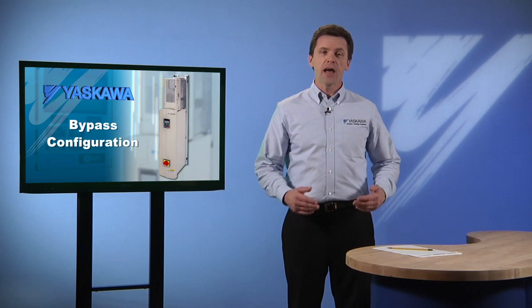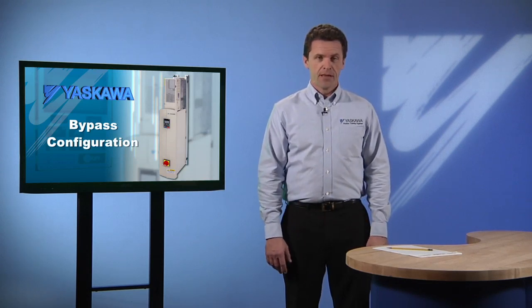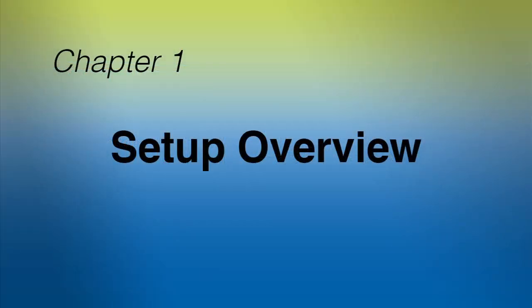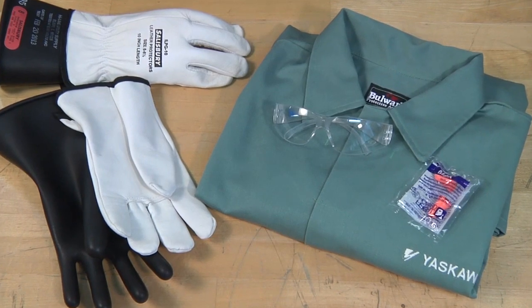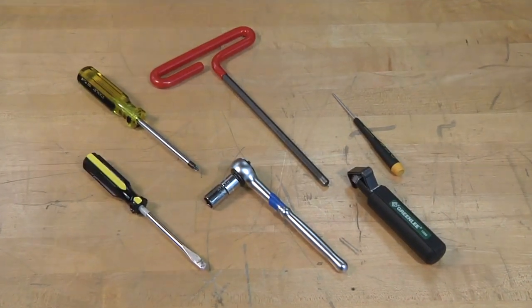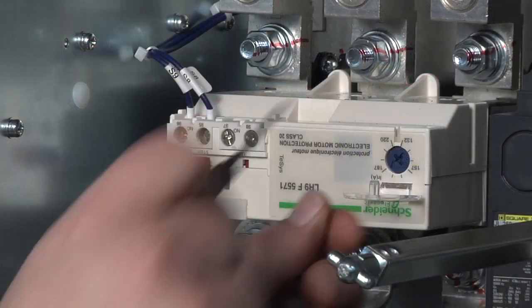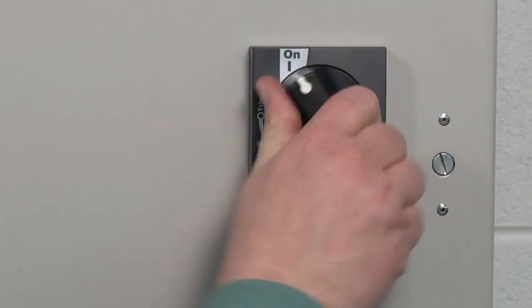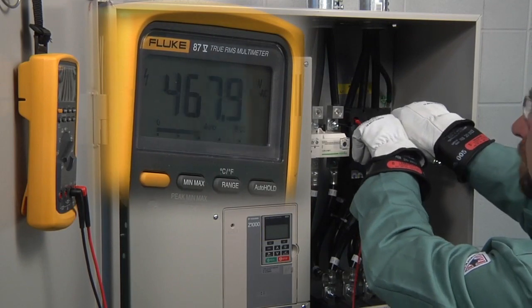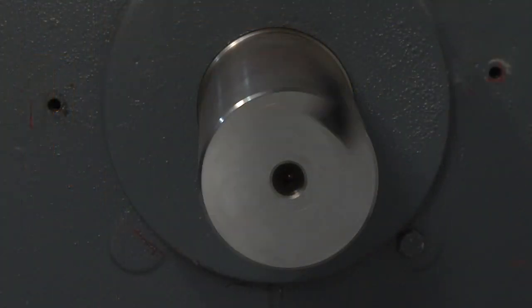It's even quicker and easier if you prepare yourself in advance with the knowledge you'll need to do the job right. So let's begin with a quick overview of the whole process. We start by gathering together the proper safety equipment and tools. Then we'll adjust the bypass to suit the load. Next, we'll apply power to the inputs and make some measurements, adjust some parameters, and test the motor for proper rotation in both bypass and drive mode. We will finish the process by adjusting the system to make sure it's working correctly and your bypass is ready to go online and function successfully.